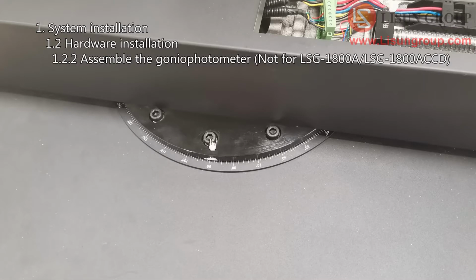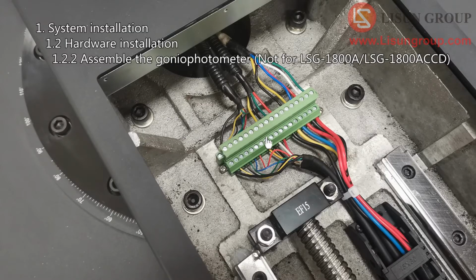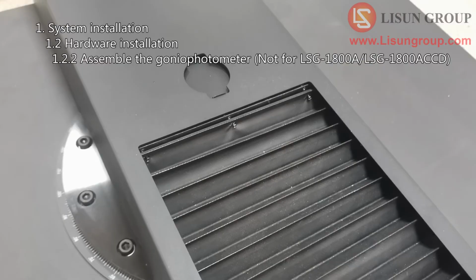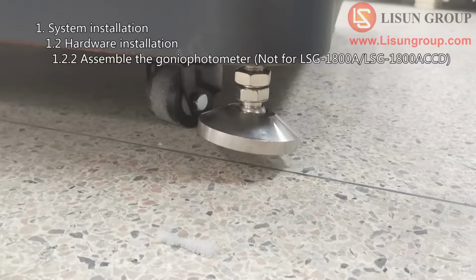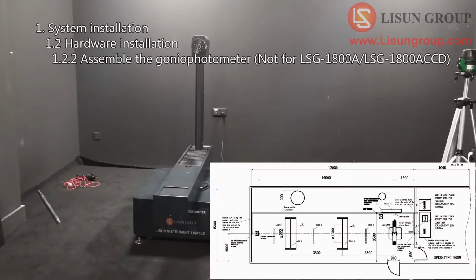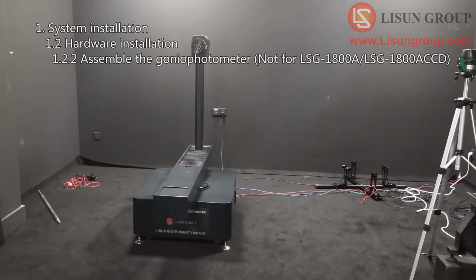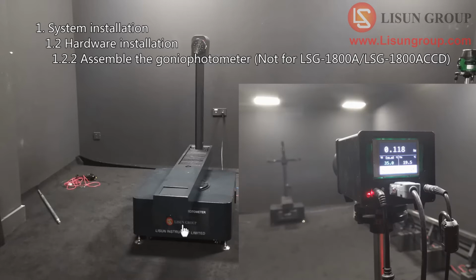Verify the direction of the turntable. Make sure that the 6 screw holes correspond to the base one by one. Fix the turntable on the base using our screws and gaskets. Connect these 2 terminal bars. Put the dust cover to its original position. Move these 4 feet up. Then move the Goniophotometer to the correct position according to the darkroom drawing. Try to keep the sides parallel to the wall. The side with the word faces the photo detector.